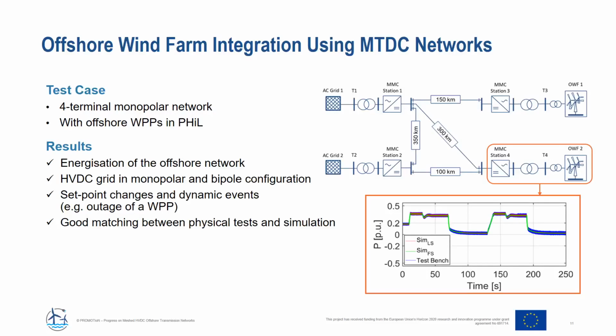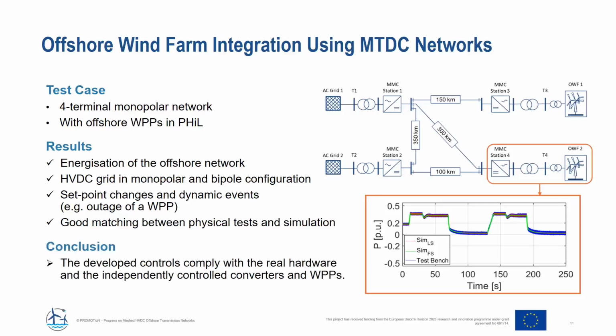Then a low-scale simulation in red, so this has exactly the same network rating, so plus minus 200 volts and 6 kilowatt per converter, and a full-scale simulation. And this full-scale simulation is then for a plus minus 320 kV network and 1.2 gigawatts per converter. Everything is scaled using a per unit scaling, and overall there is a quite good matching between the power flows here.